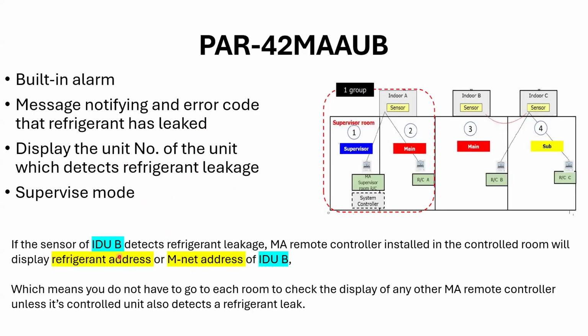If the sensor of indoor unit B detects a refrigerant leak, the MA remote controller installed in the controlled room will display the refrigerant address or MNet address of the indoor unit, which means you do not have to go to each room to check the display of any other MA remote controllers unless its controlled unit also detects a leak. So again, wherever the controller is, the unit connected to that controller is going to display the error. But they have the option of the supervisor controller. If that's in one location, it can be the supervisor and monitor those alerts also.